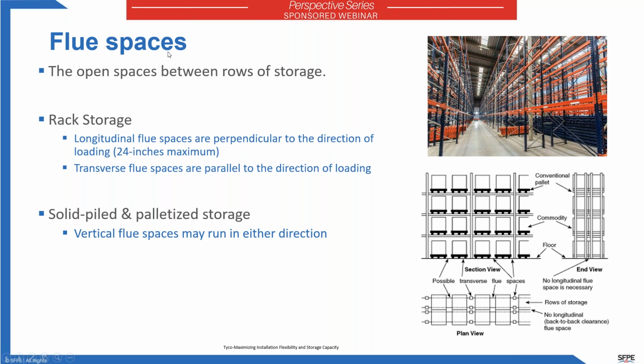A very important attribute to successful fire protection is having sufficient flue spaces. Flue spaces are essentially the spaces between the rows of storage. There are longitudinal flue spaces that are perpendicular to the direction of the loading, and transverse flue spaces that are parallel to the direction of loading. And obviously vertical flue spaces. So why are these important?